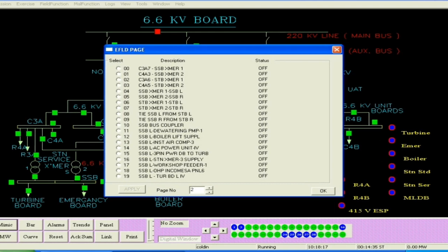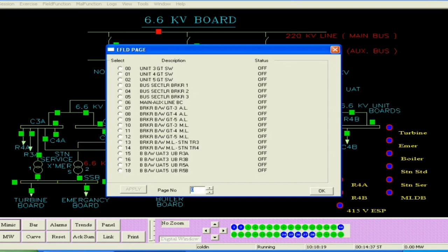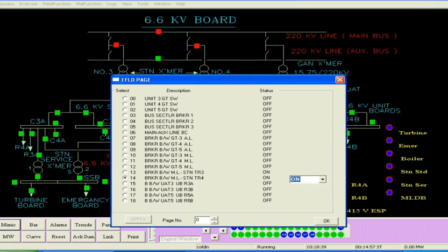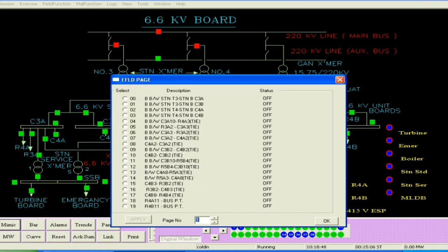So, we go to the field page number 0. We make the 13 breaker on and index number 14 breaker on. Then, after doing this, we go to page number 1. So once you make these two breakers on, you will see that the station transformers are being charged from the HV side.